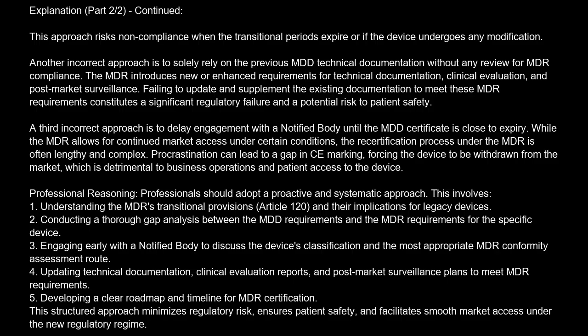Engaging early with a notified body to discuss the device's classification and the most appropriate MDR conformity assessment route. 4. Updating technical documentation, clinical evaluation reports, and post-market surveillance plans to meet MDR requirements. 5. Developing a clear roadmap and timeline for MDR certification. This structured approach minimizes regulatory risk, ensures patient safety, and facilitates smooth market access under the new regulatory regime.